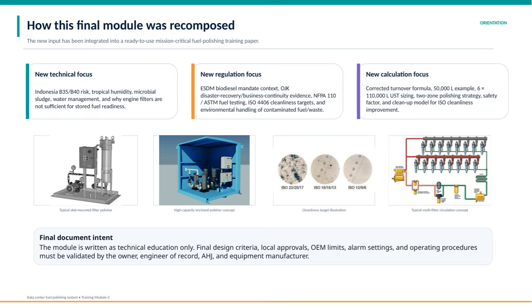We then introduce an updated calculation approach, correcting the turnover formula with practical examples like handling a 50,000-liter tank and sizing underground storage tanks at 6 times 110,000 liters. A two-zone polishing strategy, safety factors, and cleanup models are also highlighted to help improve fuel cleanliness in line with ISO standards. Visually, we explore concepts such as typical skid-mounted filter polishers, high-capacity enclosed polisher designs, cleanliness target illustrations, and multi-filter circulation setups to provide a clear understanding of equipment and system design options.